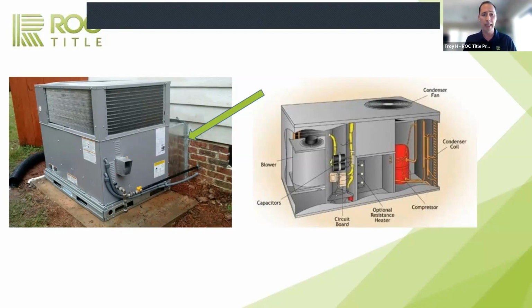What we're talking about with a gas air conditioner is you're using gas to power the system, not burning gas to make air conditioning. You still have to have a compressor and refrigerant lines for it to work. Way back in the day, they used to use ammonia gas, which I don't even think exists anymore, so it's not something you're probably going to run across. It's excluded from warranty plans because it really doesn't exist. So never confuse a gas pack with a gas air conditioner. The gas pack just means it's going to be gas heat, fired in the wintertime with natural gas or propane.